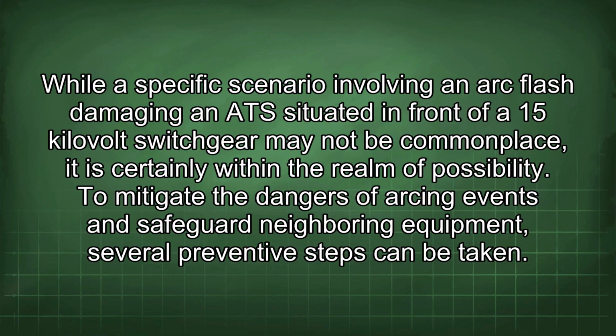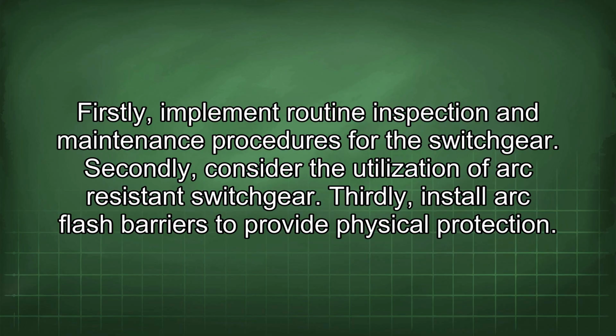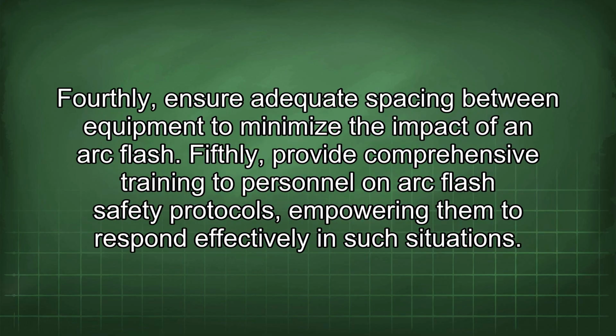To mitigate the dangers of arcing events and safeguard neighboring equipment, several preventive steps can be taken. Firstly, implement routine inspection and maintenance procedures for the switchgear. Secondly, consider the utilization of arc-resistant switchgear. Thirdly, install arc flash barriers to provide physical protection. Fourthly, ensure adequate spacing between equipment to minimize the impact of an arc flash. Fifthly, provide comprehensive training to personnel on arc flash safety protocols, empowering them to respond effectively in such situations.